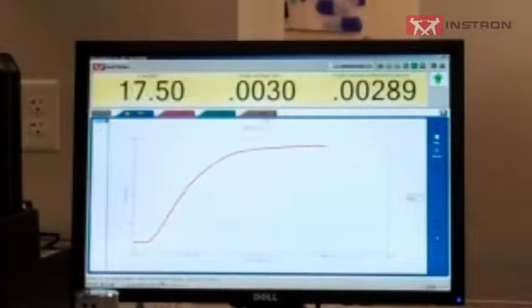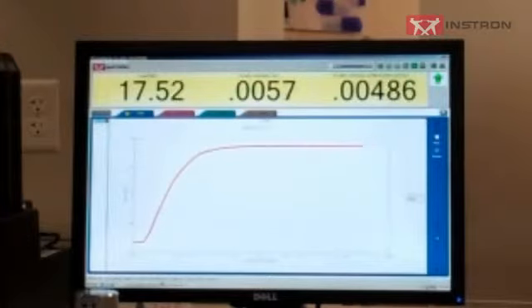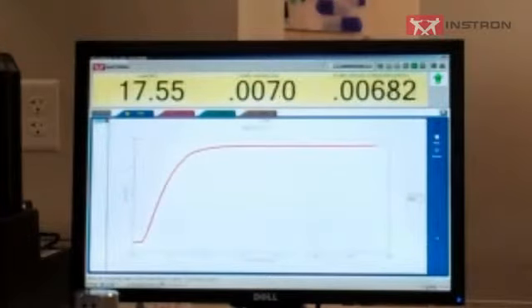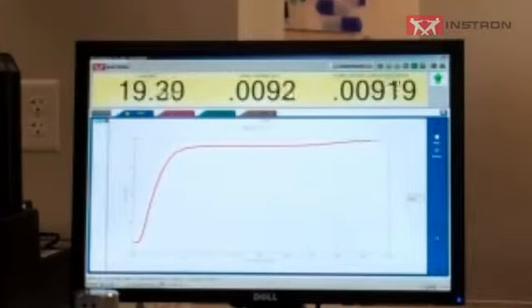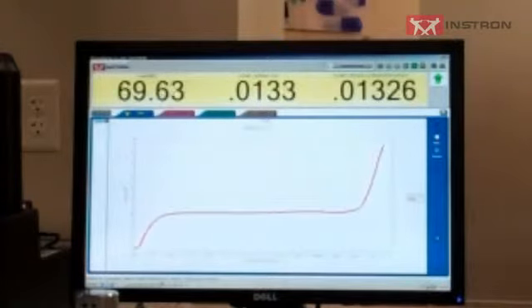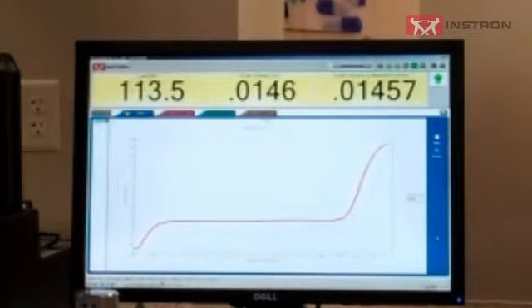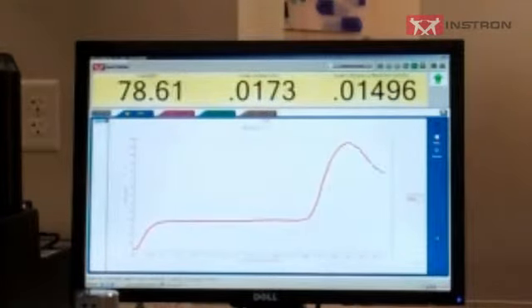So you can see there's a flat spot on the curve during the extension. That's actually just under 20 pounds, which is the weight of this grip. So it's actually lifting the lower grip through that compliance area.